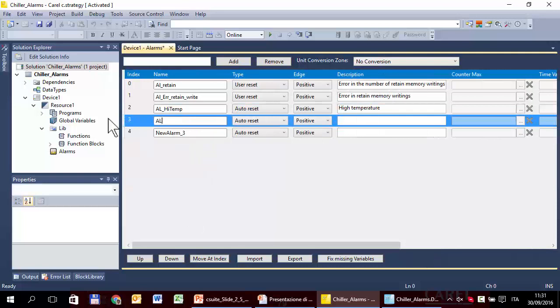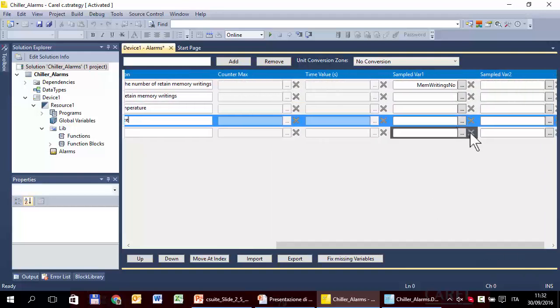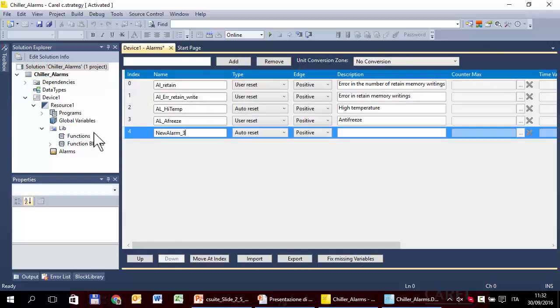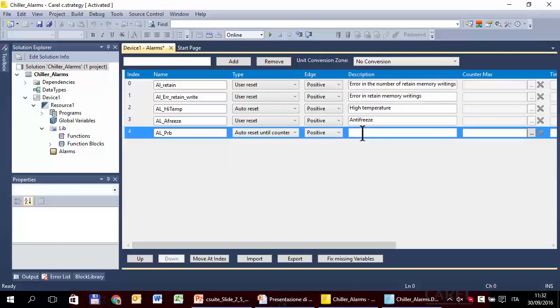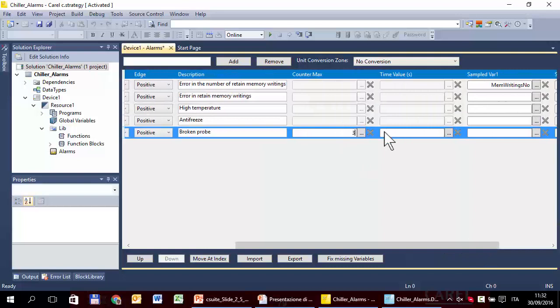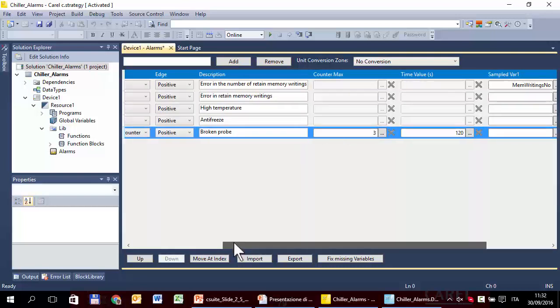The second alarm is antifreeze. This one is user reset, positive edge, with a description. The counter is not used here. In this exercise we want to use the sampled variable. The next and last is the alarm probe — broken probe — and this one uses a counter. We have to set the number and the timer. Up to two times the reset will be auto reset, and starting from the third it will be user reset.